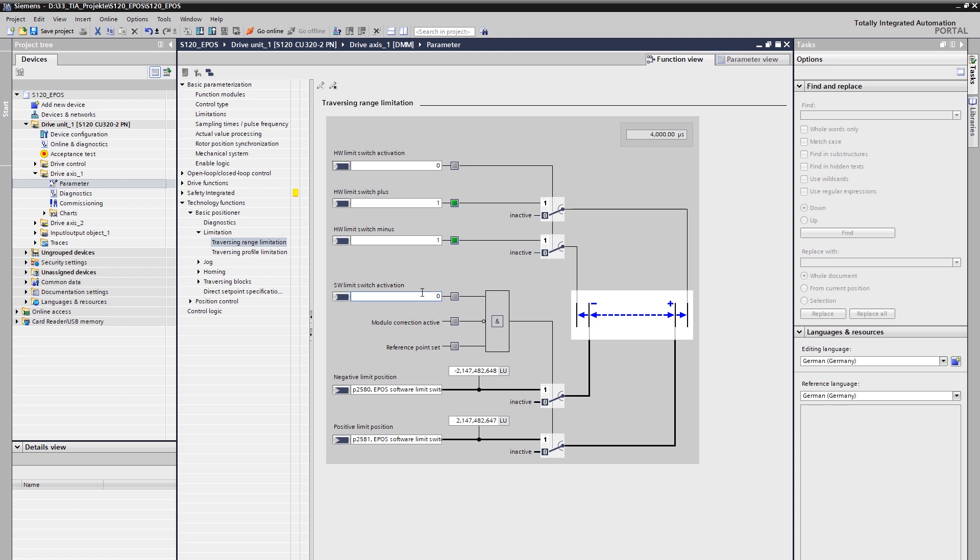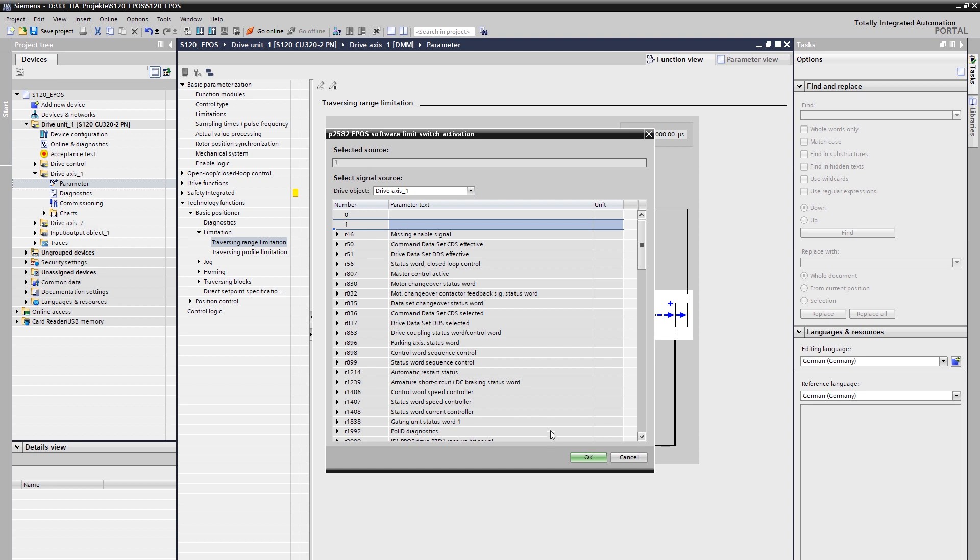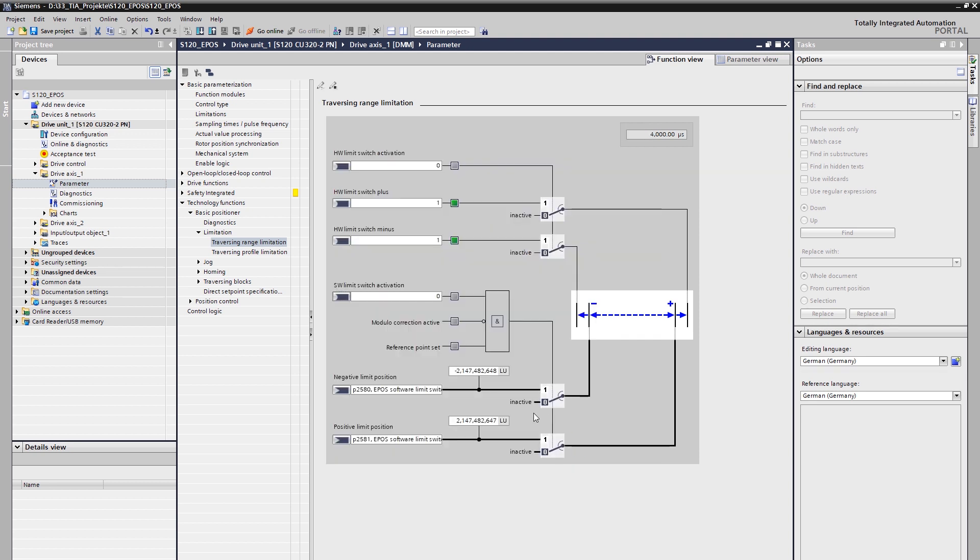The hardware limit switches, also known as stop cams, limit the travel range on the hardware side. This is done by an edge-triggered evaluation of the sensor at both endpoints of the travel range of the machine. The respective sensors of the hardware limit switches must be integrated and connected via the digital inputs. When a hardware limit switch is triggered, the motor breaks the current movement with the OFF 3 ramp. The software limit switches limit the travel range on the software side by specifying the maximum end position of the travel range. The prerequisite for this is that the axis is homed, so that it also stops at the respective end positions. The evaluation of the hardware limit switches or the software limit switches must be explicitly activated.